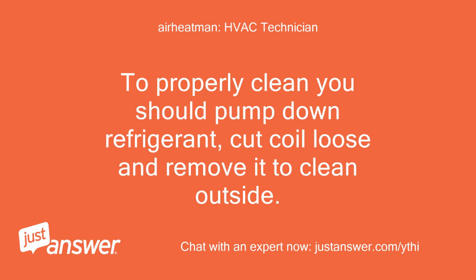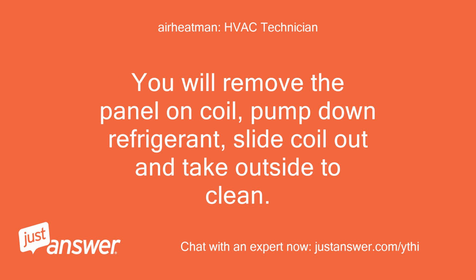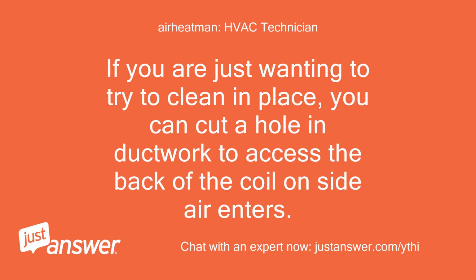To properly clean, you should pump down refrigerant, cut coil loose and remove it to clean outside. You will remove the panel on coil, pump down refrigerant, slide coil out and take outside to clean. If you are just wanting to try to clean in place, you can cut a hole in ductwork to access the back of the coil on side air enters.